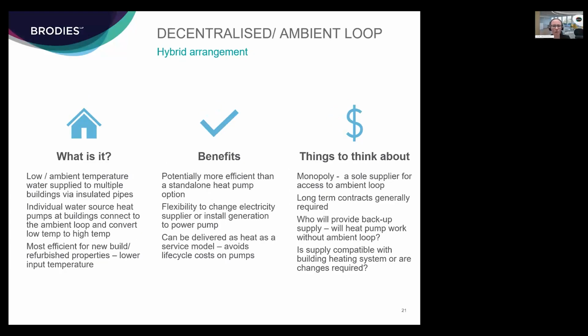So moving on to the next one, which is the decentralised system or ambient loop. This refers to a scheme where there's lower ambient temperature water supplied to multiple buildings. That can be heat from waste heat sources, from sewers or boreholes. Then you have individual water source heat pumps at the buildings that connect into the ambient loop and convert the low temperature heat to high temperature.